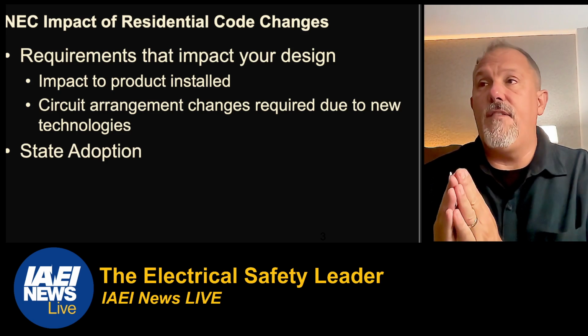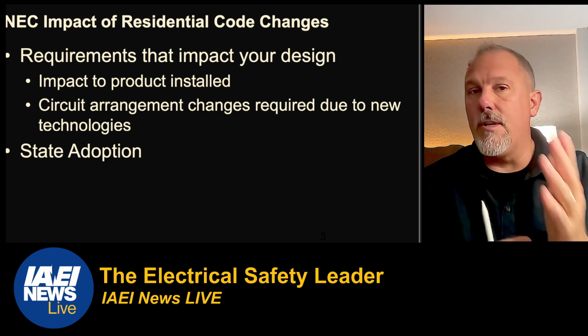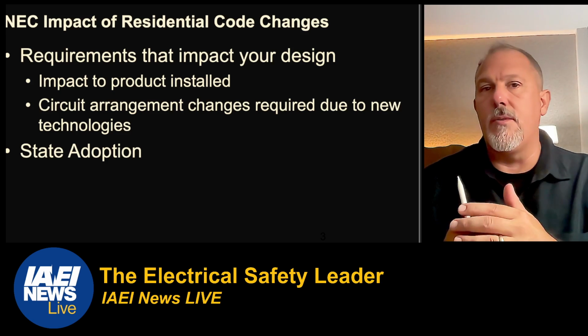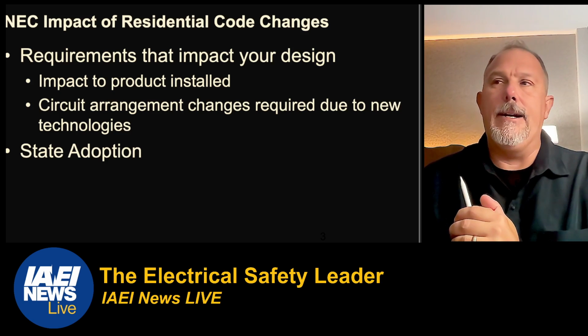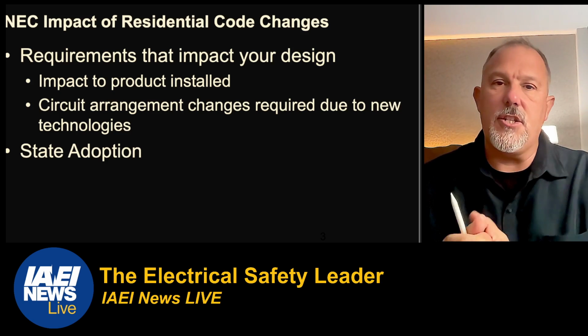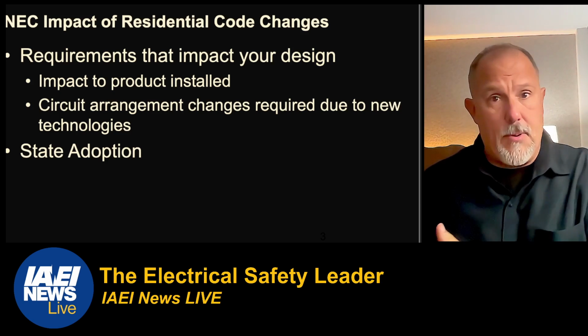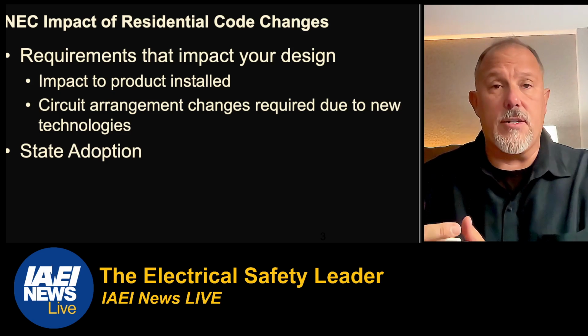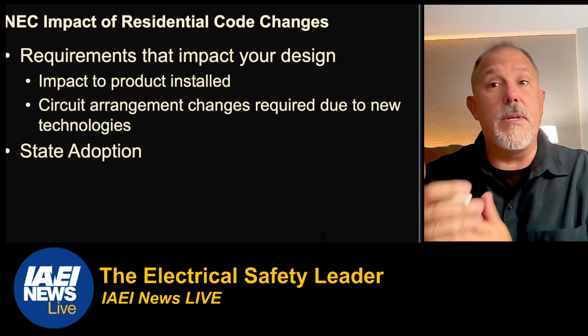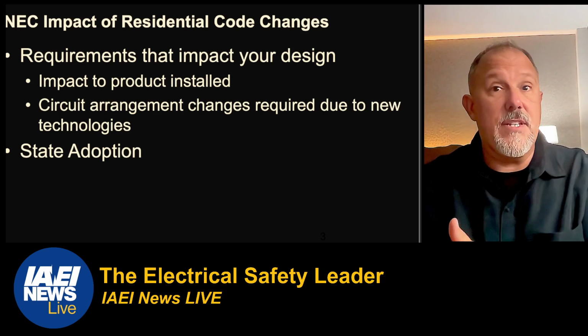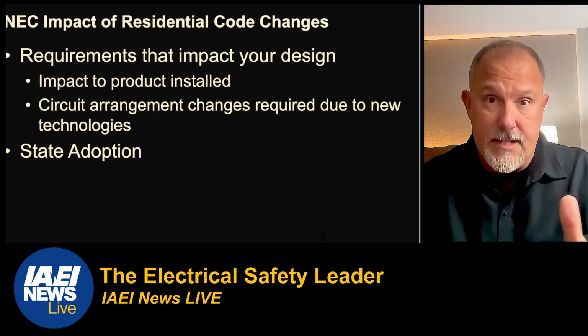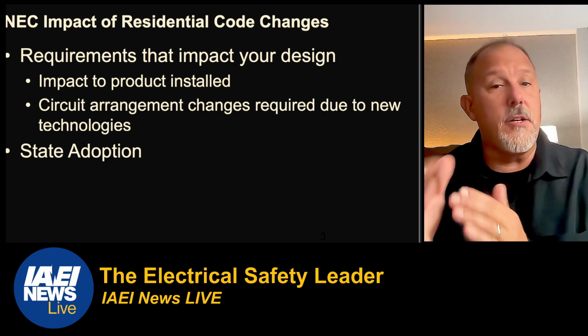For example, if you do a lot of shared neutrals and you don't want to do 2-pole breakers, but you want to do single pole breakers, in some applications you may have to change how you do your wiring practices. I know many contractors changed their wiring practices because of the technologies of AFCIs and GFCIs for a lot of different reasons. And we'll talk a little bit about that as well.